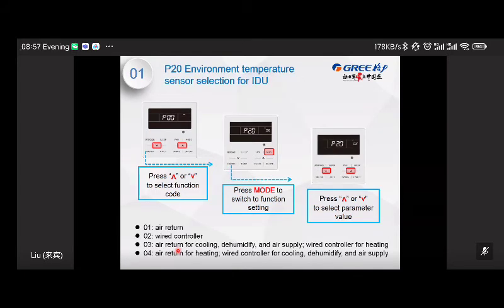Next one, P20. This is the environment temperature sensor selection for indoor unit. For the VRF indoor unit, to detect the ambient, there are two sensors. One is in the wire controller. Another one is located at the air return, at the duct. So depending on your installation and the actual demands of the customer, maybe they want to detect the ambience more precisely, so you can change the sensor's location. The default one is the air return for cooling and wire controller for heating.